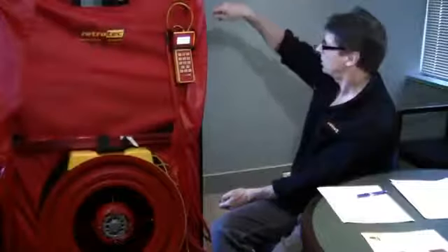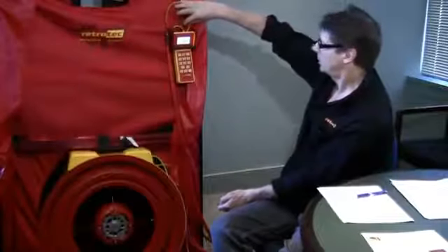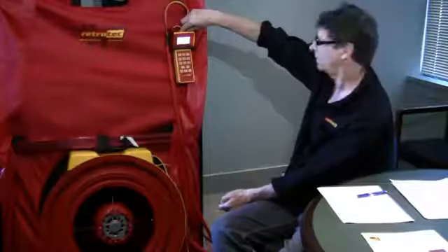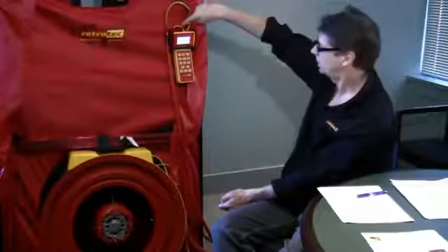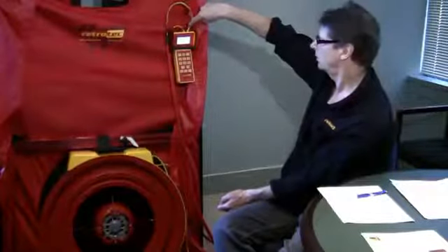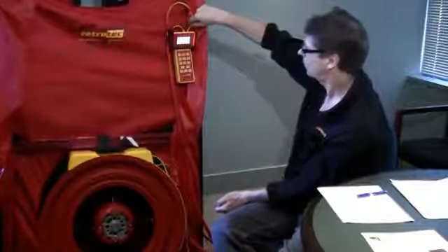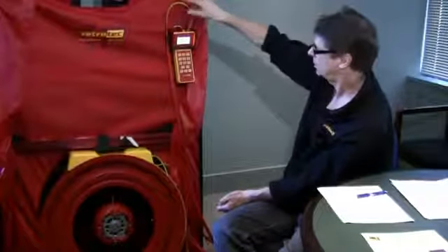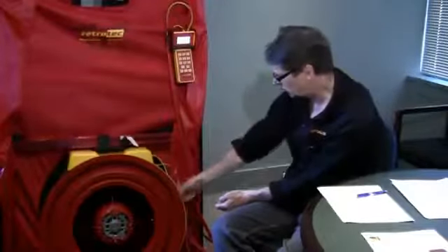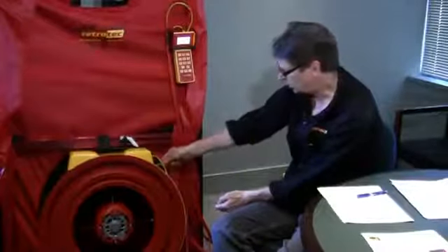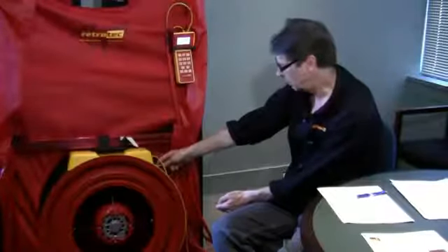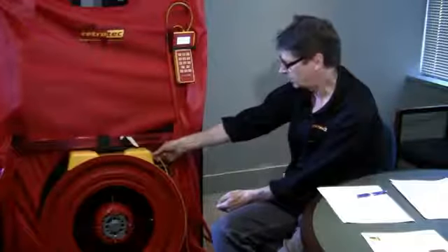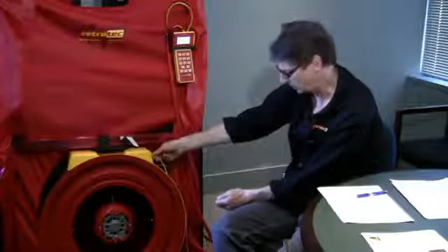A gauge setup consists of the red tube and yellow tube being connected to the red and yellow ports on the gauge, in this particular case for building pressure and for fan pressure, and a yellow Ethernet cable which comes out, which is a control cable. This comes down over towards the fan, and the yellow connector goes into the fan onto the reference B port, and the Ethernet cable, which is the controlling cable, goes into the fan.